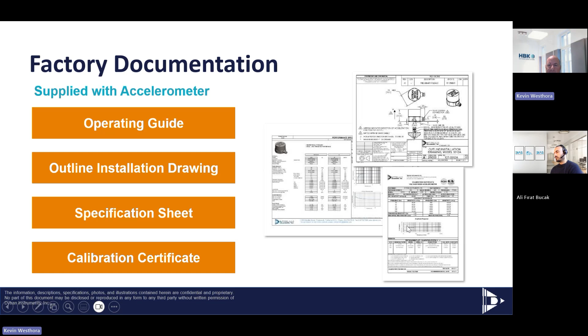And then the last sheet here is our calibration certificate that comes with every accelerometer. We usually start at 20 hertz and go up to 10 kilohertz. And then we give you 10 points of data, and then we plot those 10 points down here for the response amplitude curve for frequency. We can go down to 1 hertz if you need it. You just need to let us know, and we can go up to 17 kilohertz. We are accredited from ISO from 1 hertz to 10 kilohertz for calibrating accelerometers. Okay. And just a reminder, the calibration data point that you'll see on your box, on the accelerometer box, the sticker, is the 100 hertz data point. That's the reference sensitivity that every accelerometer company uses, 100 hertz.